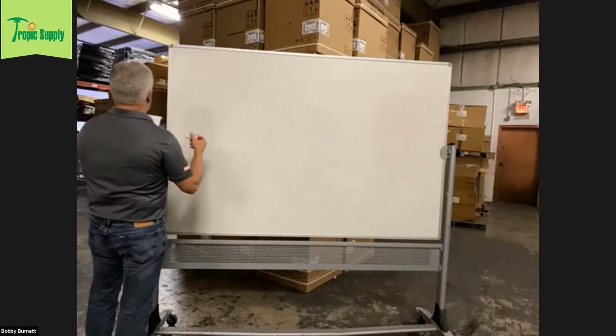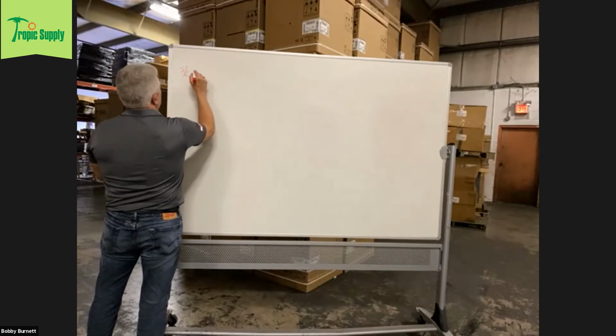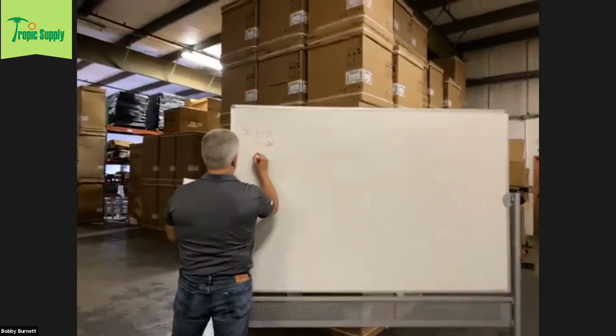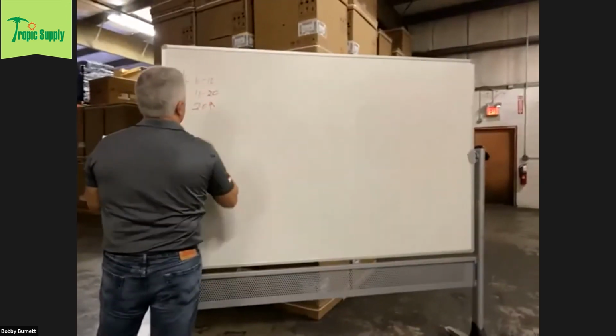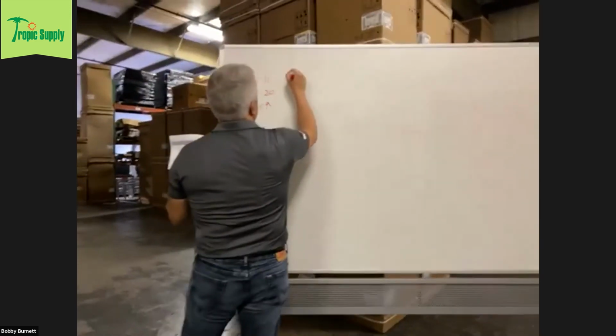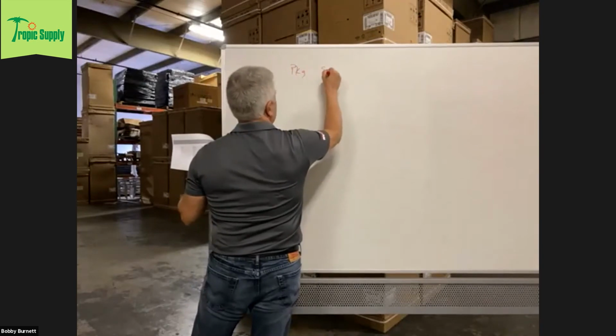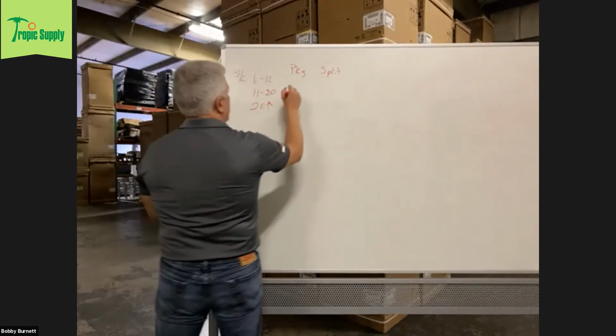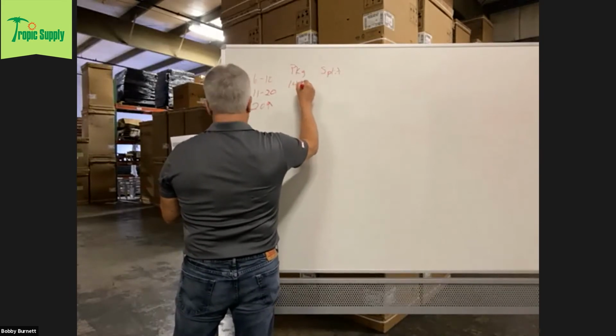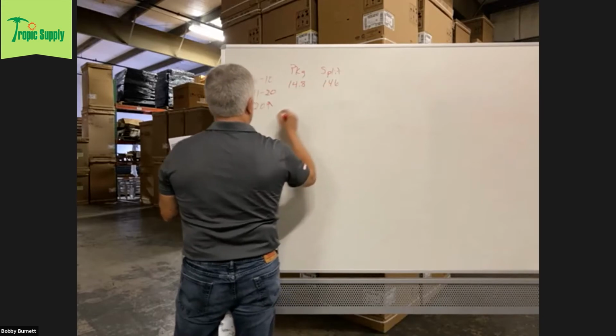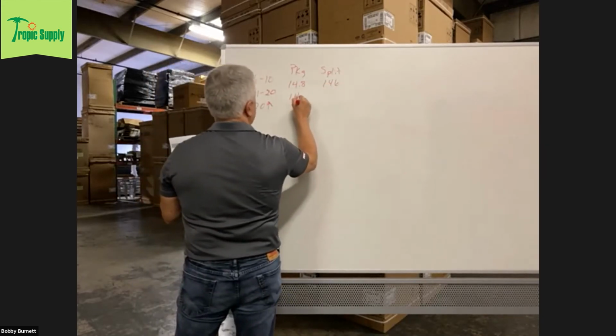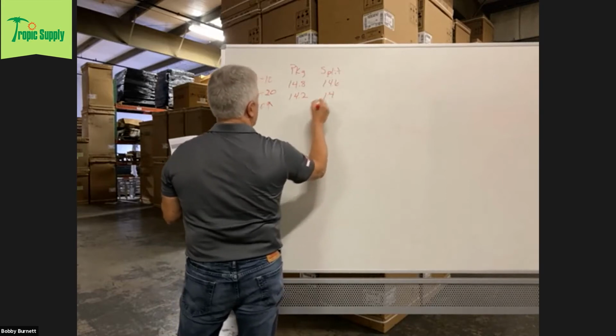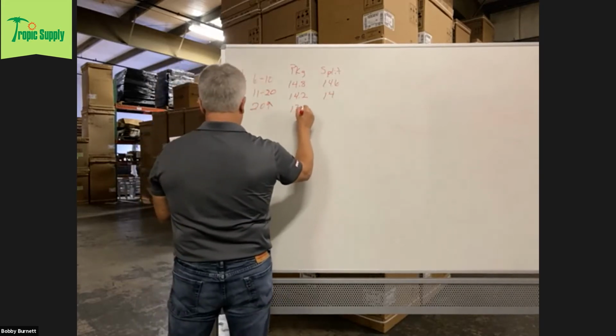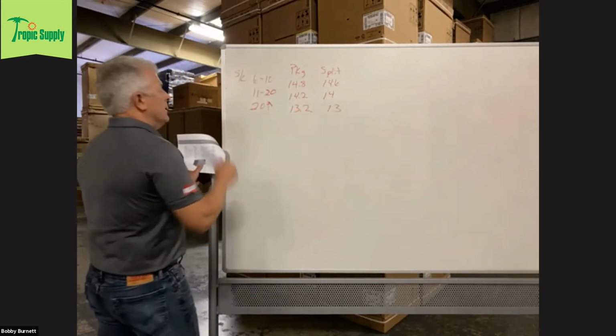When we're talking about the efficiencies, and yes, I have a cheat sheet because I can't remember all these numbers, on your straight cool equipment, you have your 6 through 10 ton, your 11 through 20 ton, and then your 20 ton and up. Your efficiencies are split up into package units and split systems. On 6 through 10 ton you're looking at an IEER of 14.8 and 14.6. On your 11 through 20 ton, you're looking at 14.2 on the package units, 14 on the split, and on 20 ton and up, 13.2 and 13. Okay, those are straight cool.